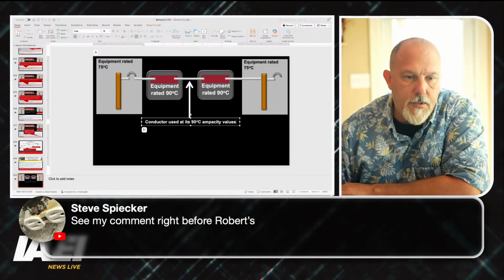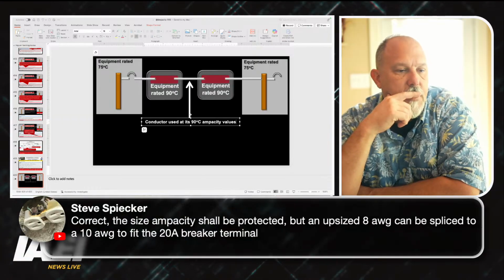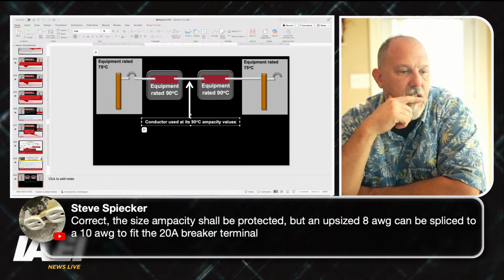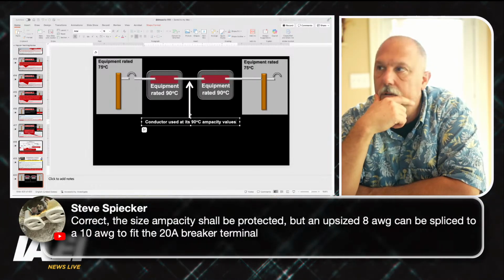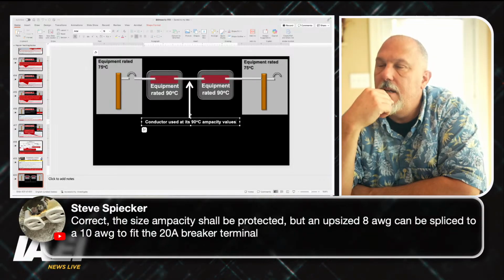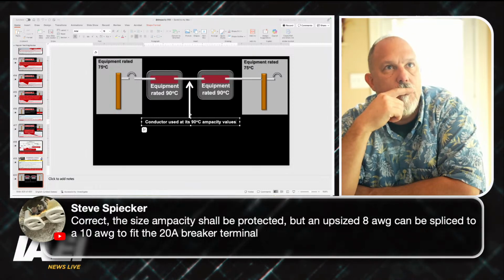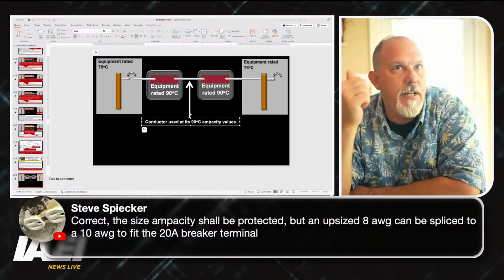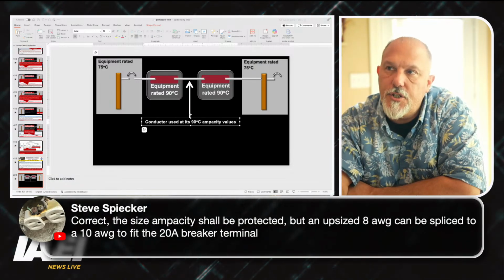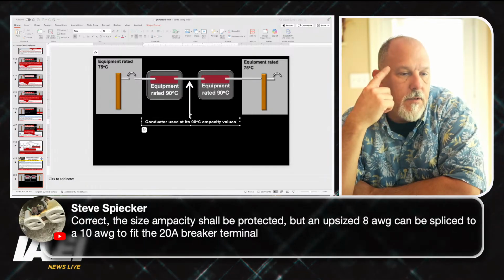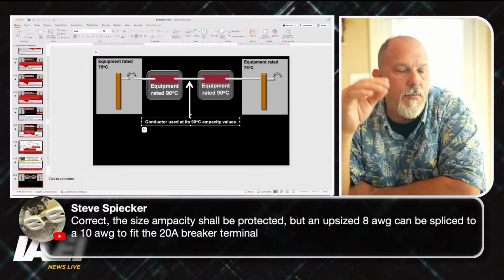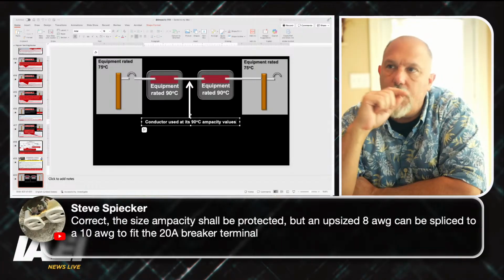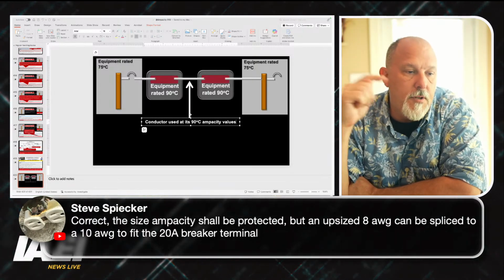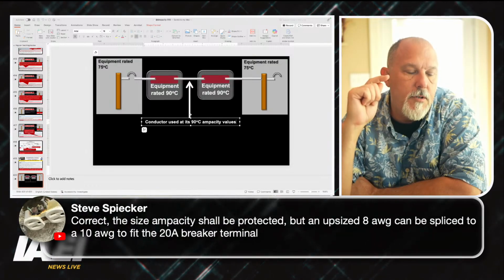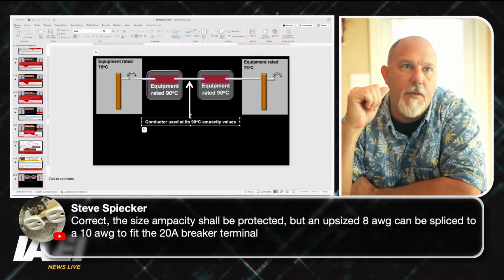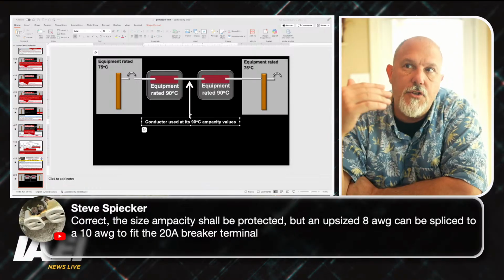See my comment right before Robert's. Correct. The size ampacity shall be protected, but an upsized 8 gauge can be spliced to a 10 gauge to fit the 20 amp breaker terminal. Depends on the conditions of use, I know that. And what you're doing is you're basically going to a size larger conductor. So you're going to a larger conductor, not a smaller conductor, so that you can put that into the 20 amp circuit breaker terminal. Yeah, you can do that. You're perfectly fine because you've gone to a larger conductor, even if it's used at 75 degrees C.